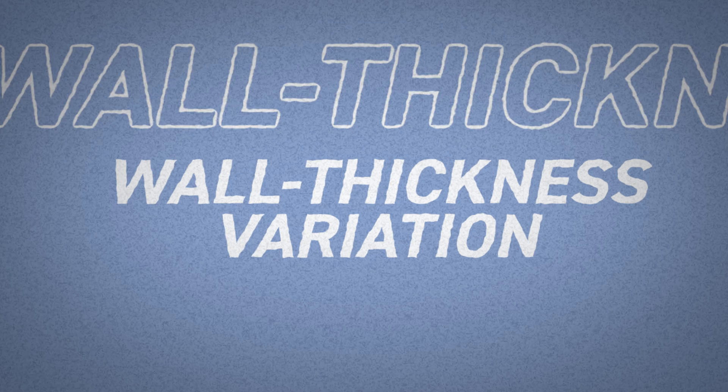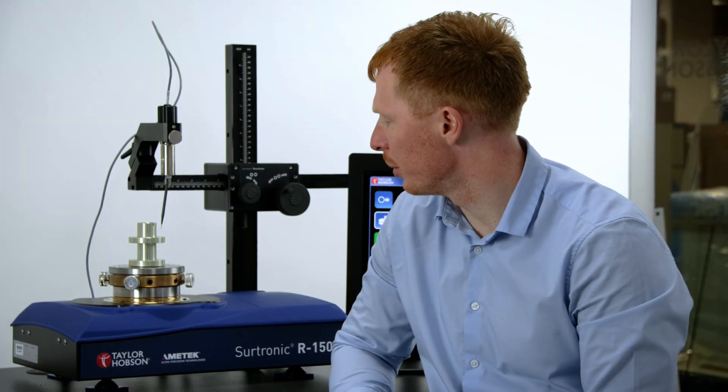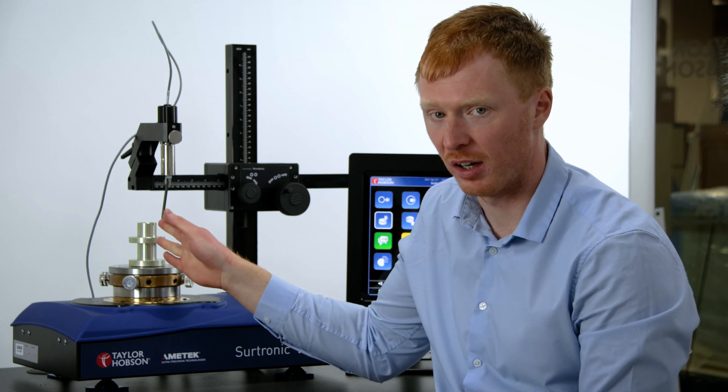The next measurement we're going to take a look at is wall thickness variation. The great feature is that we can measure over center, which means there's no need to orientate the gauge between measurements. This is really important for production environments where we want fast measurements.